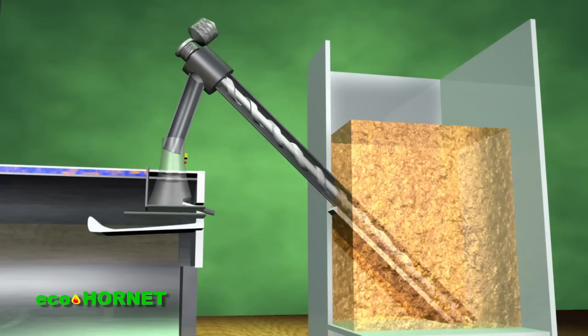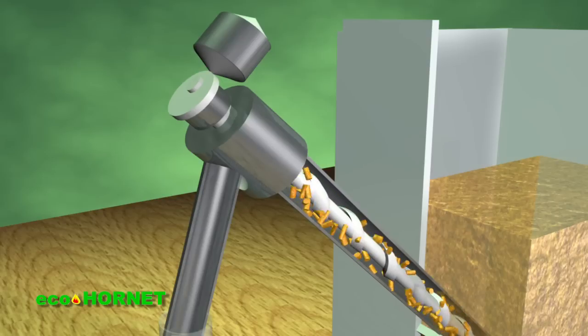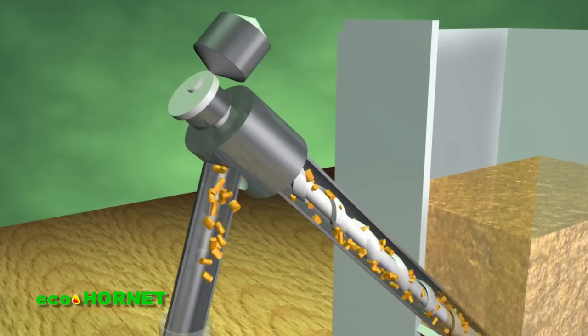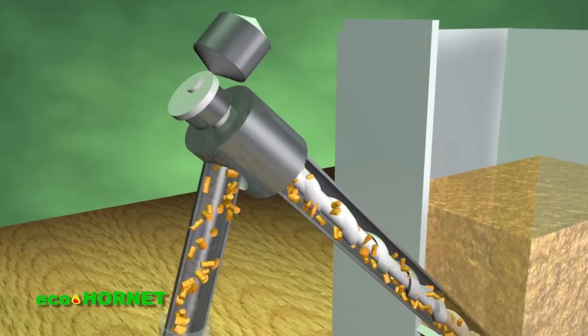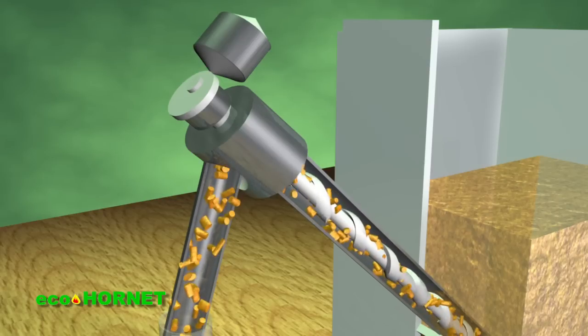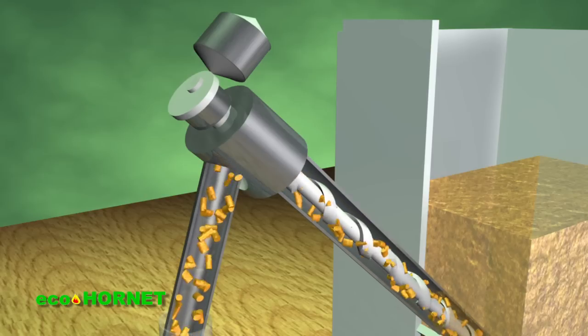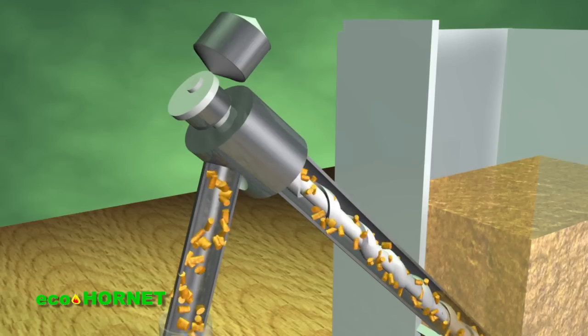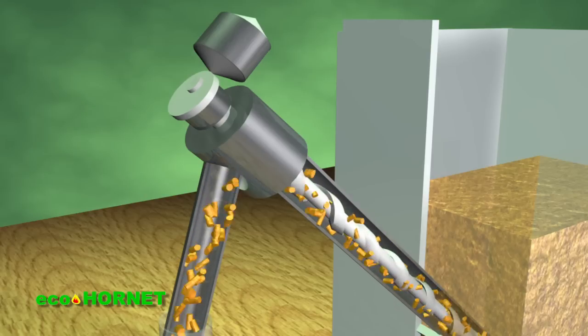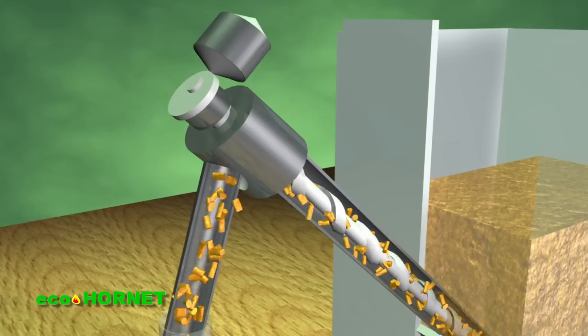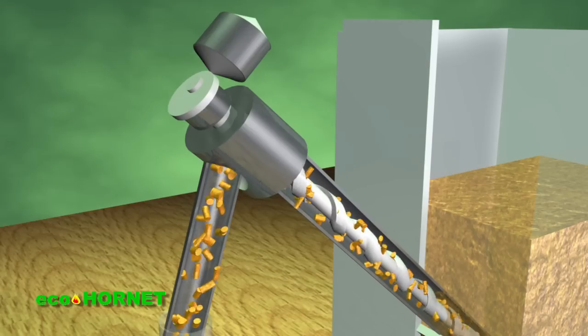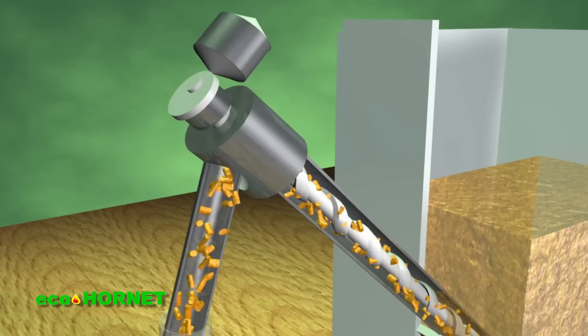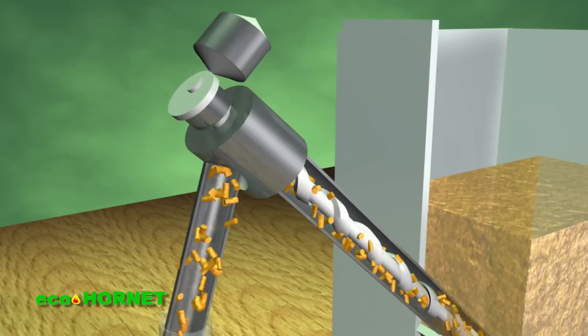When the power button of the heating system is pressed, the worm gear is set in motion, and the burner is filled with pellets. From the bunker, the pellets are taken over by a worm device operated by a 24-volt DC motor, heat protected. Thermal protection is a must in order to avoid the destruction of the gear mechanism, in case very moist pellets are introduced in the bunker or pieces of wood or metal have reached the bunker either from the pellets or during resupply.